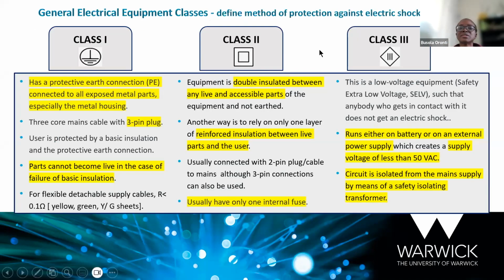So, talking about medical devices, we have 3 classes. We have classes 1 to 3, and you can see the symbols, like they have nameplates. Medical equipment generally has nameplates, or if you look under them or somewhere, they will have some details about them. If you see this symbol, you know that's a class 1 equipment, or sometimes there will be no symbol. If there is no symbol, it's a class 1 equipment. This shows a class 2 equipment, and this is a class 3 equipment.